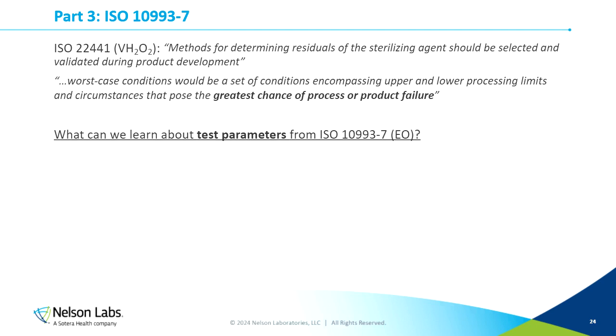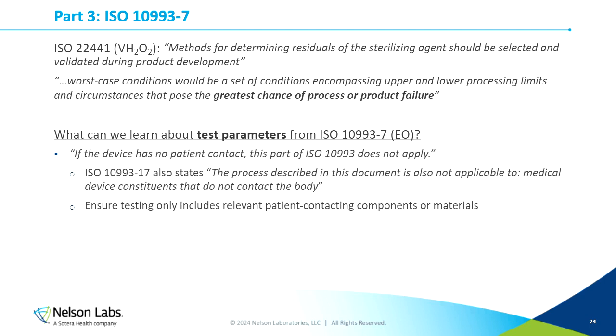Okay, so now we know the device that we're testing. We selected a representative product, and we know how we're sterilizing it, and we know how we're sending it to the lab. What about testing parameters? What can we learn about this from the ethylene oxide standard? First of all, this is a very important one, which is just part of the ISO 10993 series on biocompatibility, which is if a device has no patient contact, ISO 10993 does not apply.